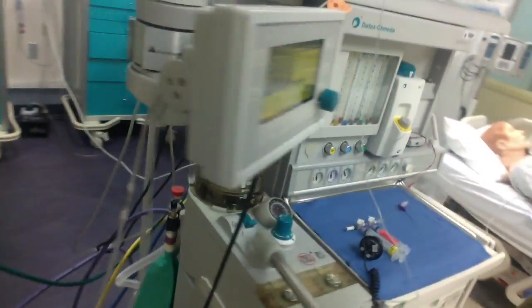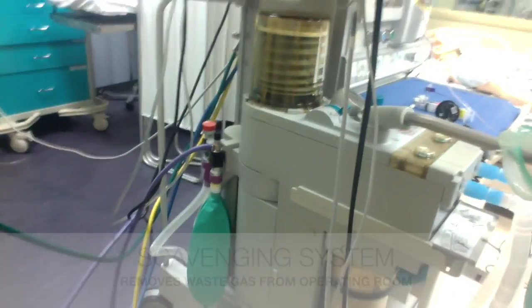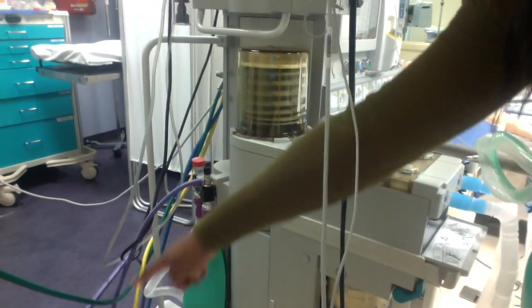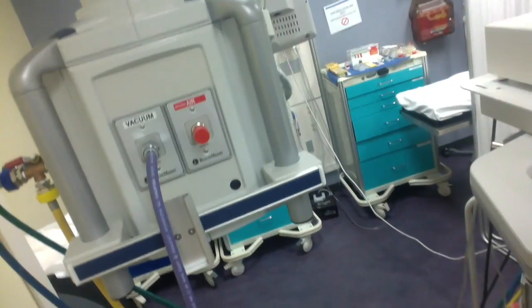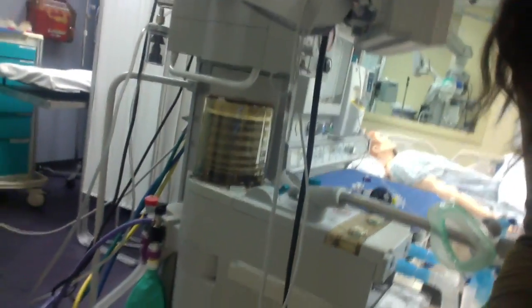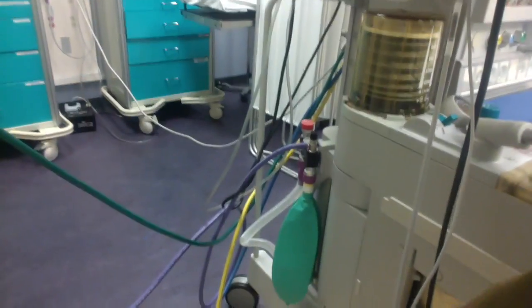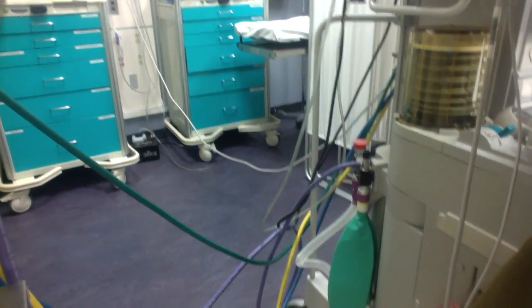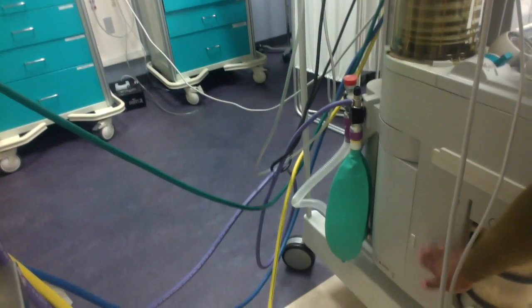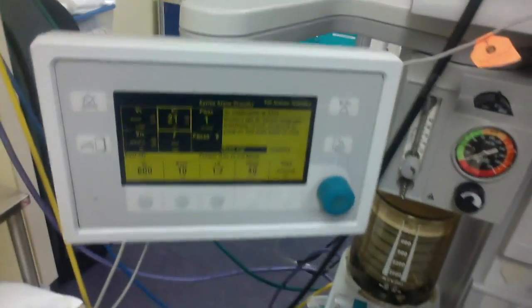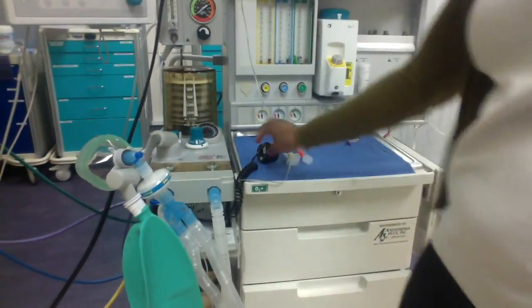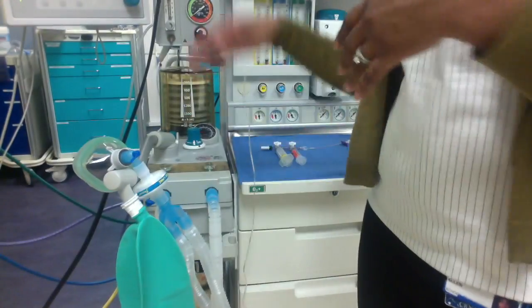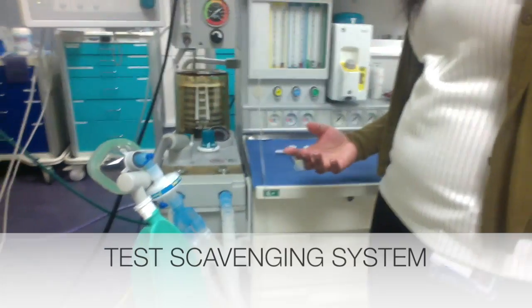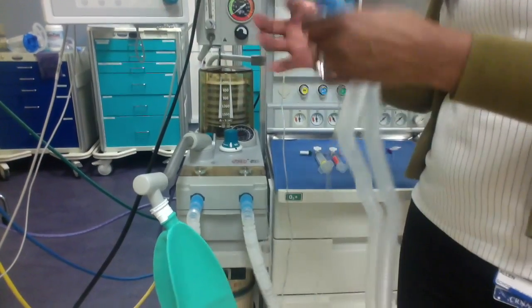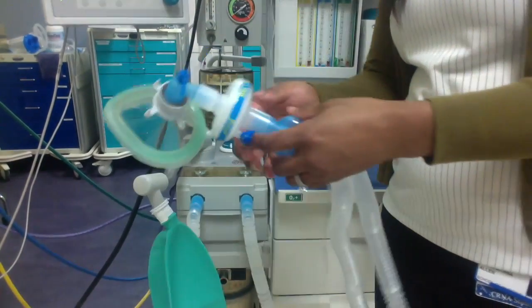So I would also come around here while this is still calibrating and look at what is called my scavenging system. That scavenges waste air and sends it to a vacuum, that purple one that says vacuum, and takes it out of the room. So we're not breathing in a bunch of gas. Otherwise we'll go to sleep. So I also want to make sure that the bag is flat, and that some machines have a ball here that tells you that it's suctioning appropriately. This now says complete, so I'll take this cap and screw that back on. Now that I've visually inspected my scavenging system, I'm going to actually test it now. So to do that, I grab my circuit. This is the mouthpiece, HME, and the Y piece.